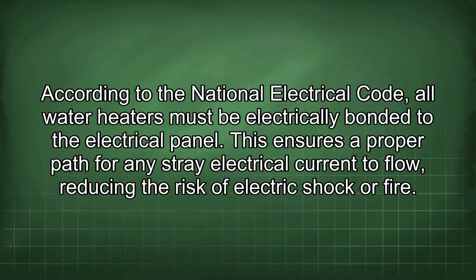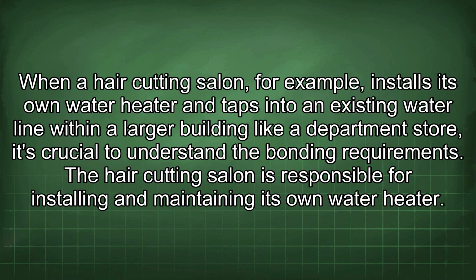According to the National Electrical Code, all water heaters must be electrically bonded to the electrical panel. This ensures a proper path for any stray electrical current to flow, reducing the risk of electric shock or fire. When a haircutting salon, for example, installs its own water heater and taps into an existing water line within a larger building like a department store, it's crucial to understand the bonding requirements.